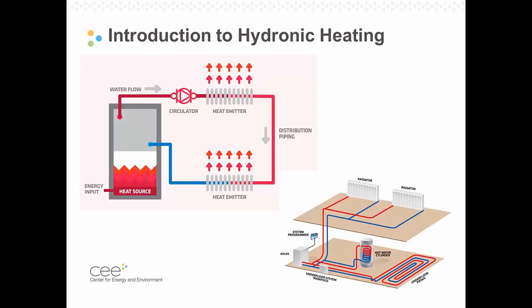So just to give a brief overview of hydronic heating, these are two diagrams of the basics of hydronic heating systems. You basically have a boiler that has the combustion process going on inside of a heat exchanger, and that heat exchanges to water that then gets piped out to emitters or radiators. There's definitely more simple versions and more complex versions, and you can see two examples of that here on the slide. The diagram in the bottom right shows a system that also includes, in addition to radiators, an in-floor heating loop as well as an indirect water loop, all being powered by the combustion heat of the boiler.